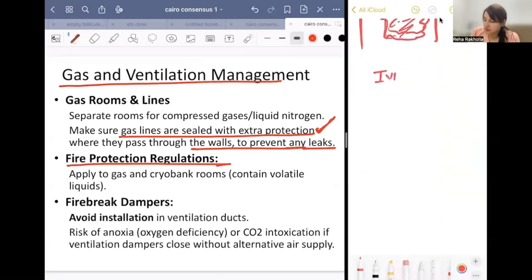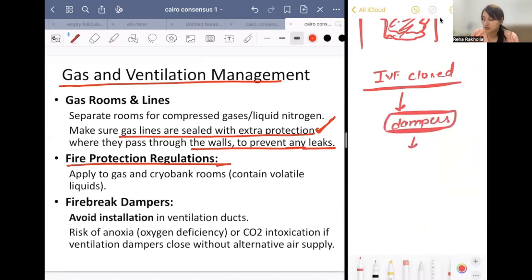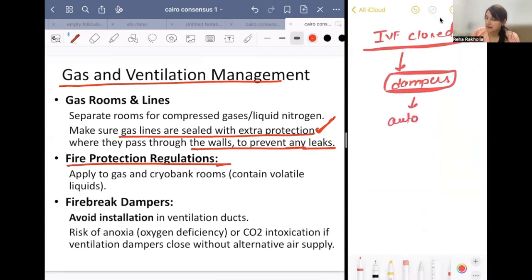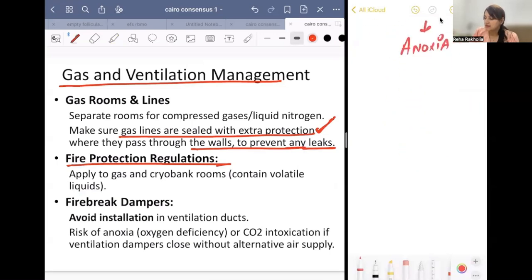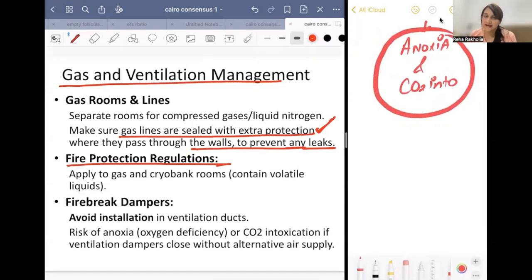But the IVF lab is a closed space. There is no window, nothing. So if we use dampers in it, sometimes the dampers can close automatically. If dampers close automatically, there will be a risk of anoxia and CO2 intoxication, because there won't be any alternate air supply in the IVF lab. It is a closed lab and a closed chamber. So we cannot use dampers in the IVF lab.